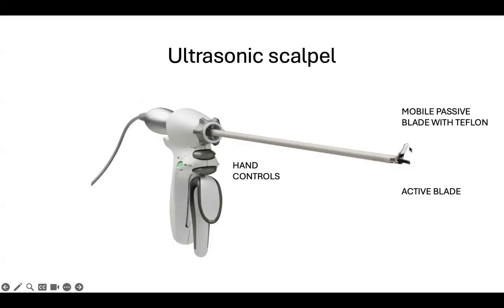This blade has no action in coagulation, no action in cutting. It only acts as a support. And the second blade you see is the active blade. This is the blade which is going to vibrate at 55,000 hertz, or 55,000 cycles per second. And this passive blade is only used for support.